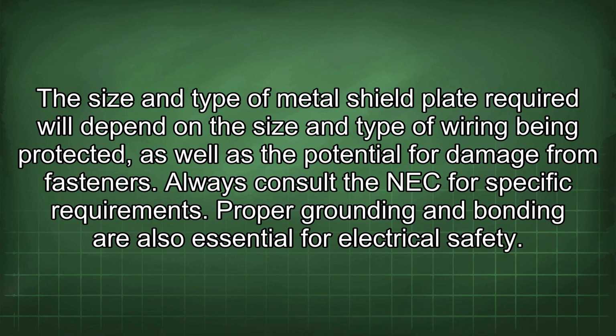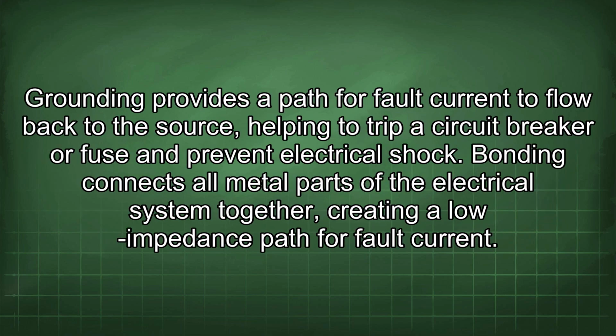Proper grounding and bonding are also essential for electrical safety. Grounding provides a path for fault current to flow back to the source, helping to trip a circuit breaker or fuse and prevent electrical shock. Bonding connects all metal parts of the electrical system together, creating a low impedance path for fault current.